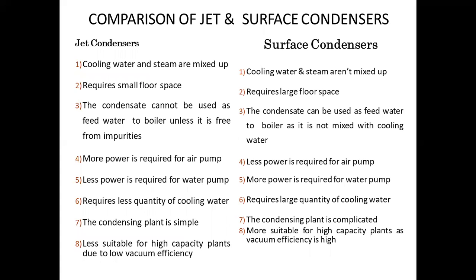If we are comparing jet condenser and surface condenser, you can see there is a comparison that in case of jet condenser, cooling water and steam are mixed up, while in surface condenser they are separate. Jet condenser requires small floor space, while surface condenser requires more floor space. Jet condenser condensate cannot be used as feed water because it is not free from impurities, while the condensate in surface condenser can be used directly as feed water because it is free from impurities.